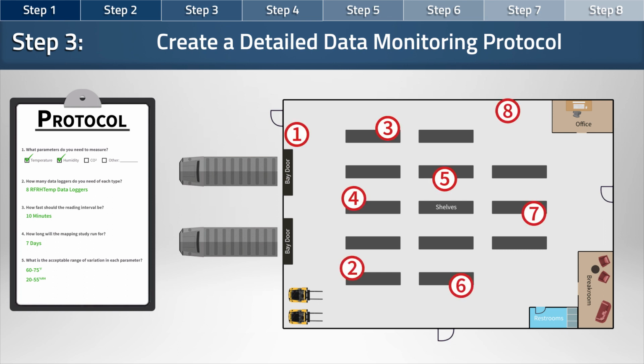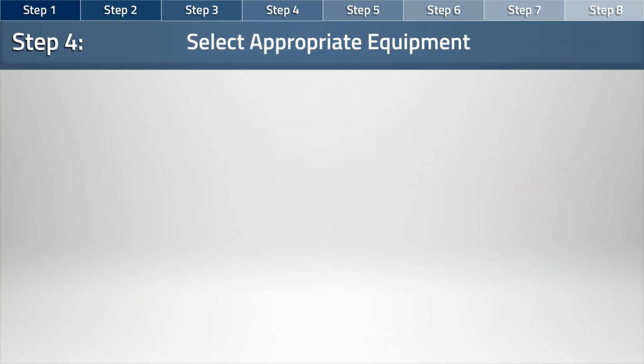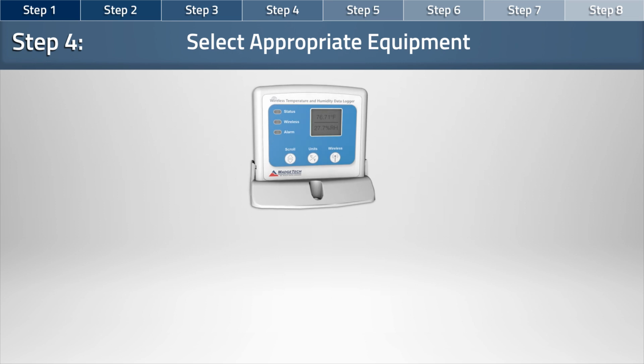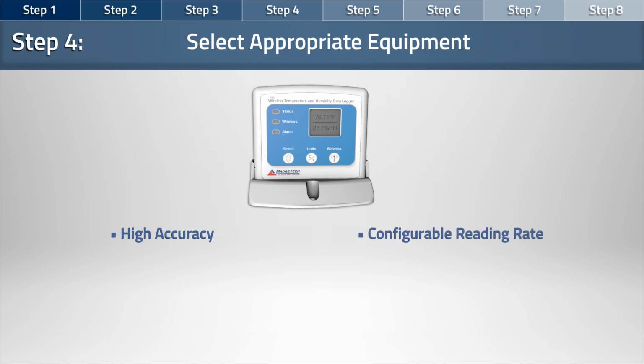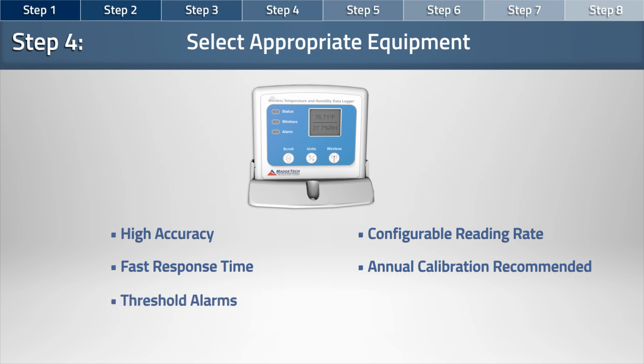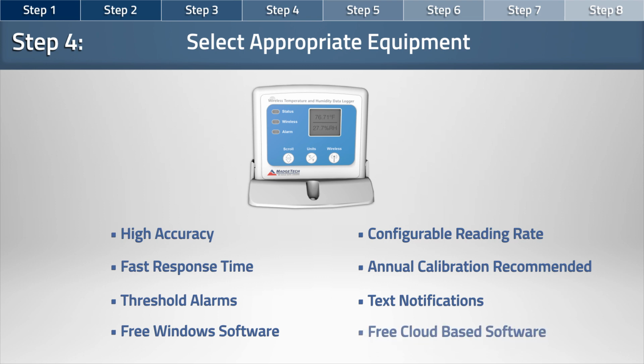Now that all plans are laid out, it's time to move on to the fourth step, selecting the appropriate equipment. Some specifications to look for in a data logger are: high accuracy readings, a configurable reading rate, a fast response time, maintenance and calibration requirements, user-defined threshold alarms and notifications, and an easy-to-use software for analyzing data.